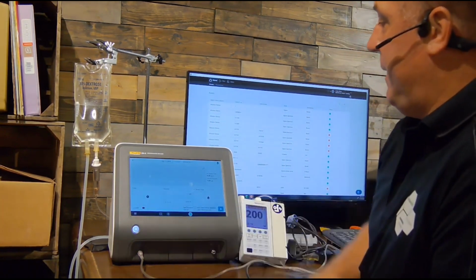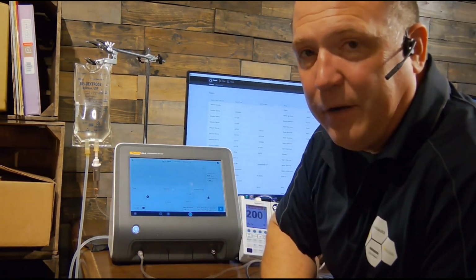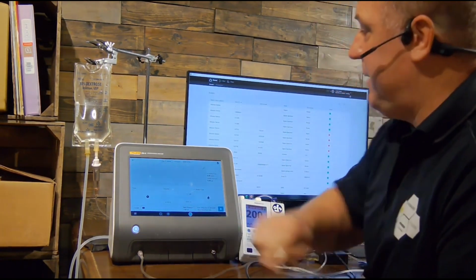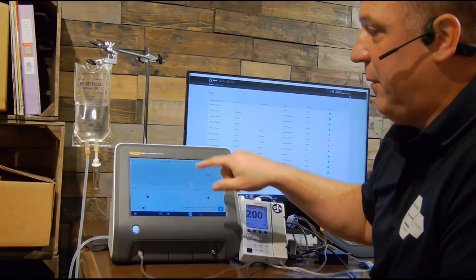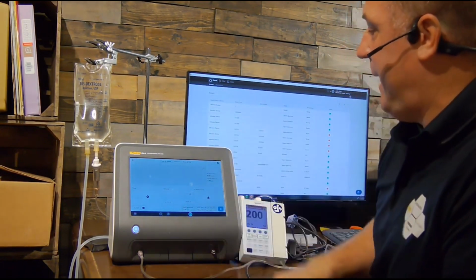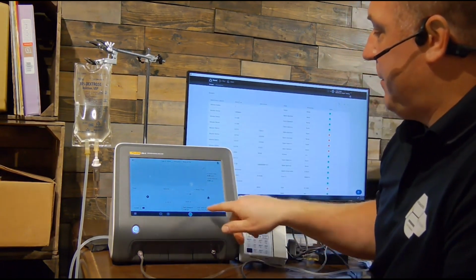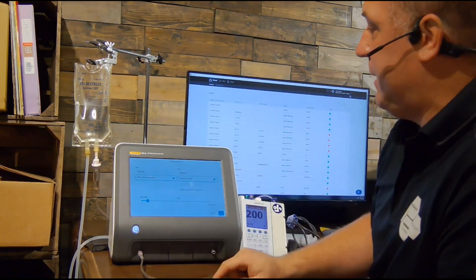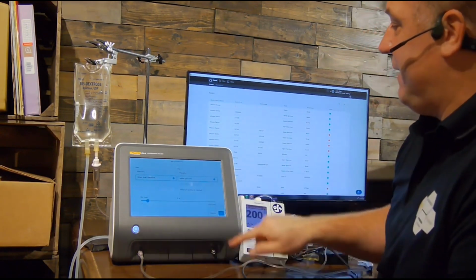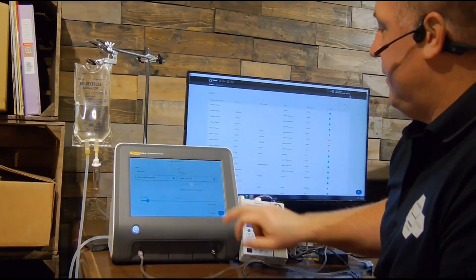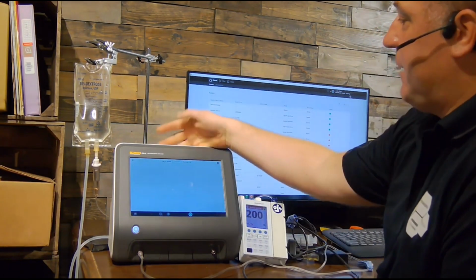Okay, back to channel 4. I can add my notes into it, and I can introduce back pressure. So if I'm an OEM doing some testing, or I have specific tests where I want to sense back pressure, I can add that. I can also program when my IV pump will start and stop, and extend that delay for when it stops. All of that is here, along with my occlusion screen.